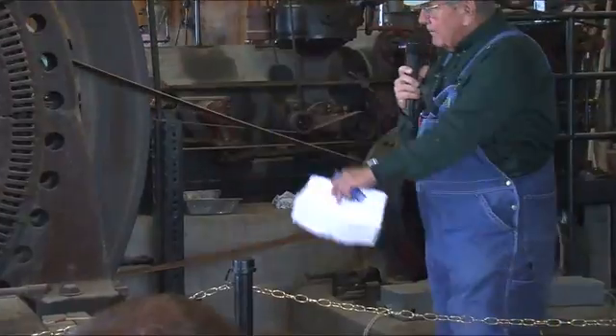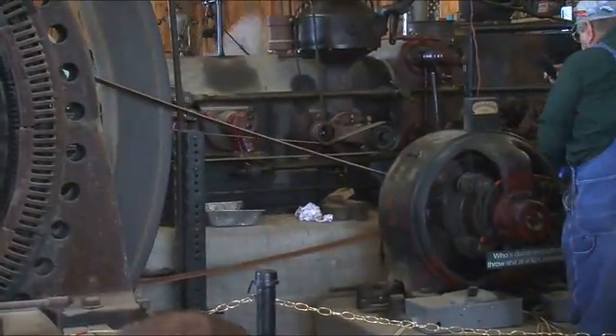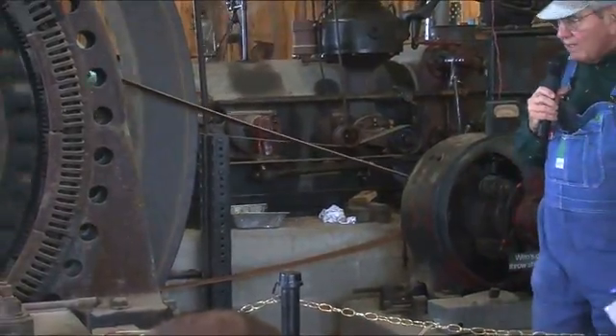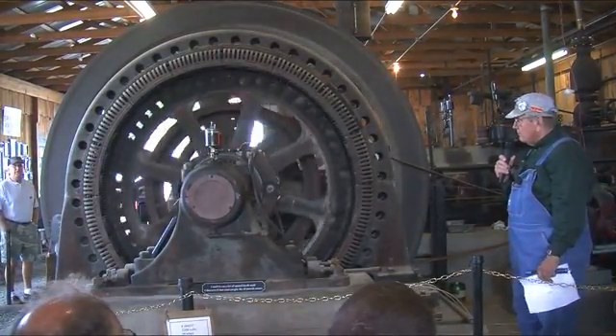It has an exciter — it must have an exciter to produce DC to excite the windings. This is basically a DC generator. It puts out 125 volts, 100 amps. Its purpose is to excite the windings in the alternator so that the alternator can produce the 2,300 volts it is designed to do. In order to do this, the engine has to be running at 150 RPM.